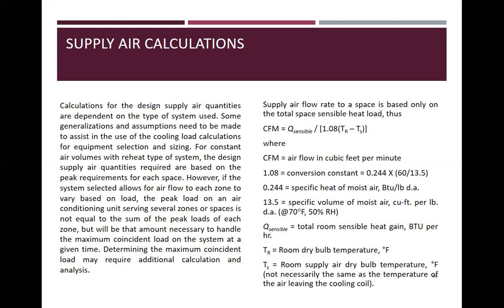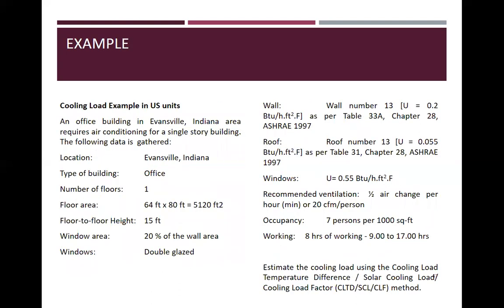Okay? Hindi siya saturated. And this is 20 degrees below the room temperature, Fahrenheit. So, di na in-explain dito kung anong difference. Pero normally is 20 degrees Fahrenheit. Okay, kung 75 Fahrenheit ang room mo, 55 Fahrenheit ang supply temperature mo.